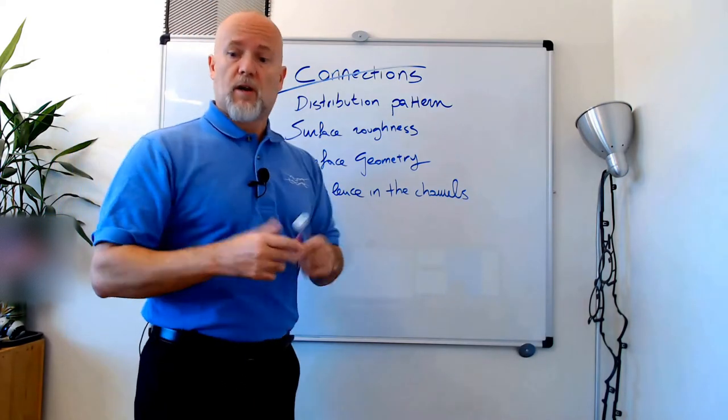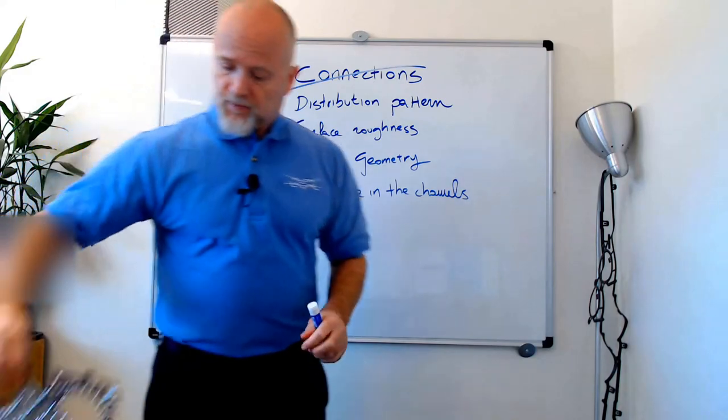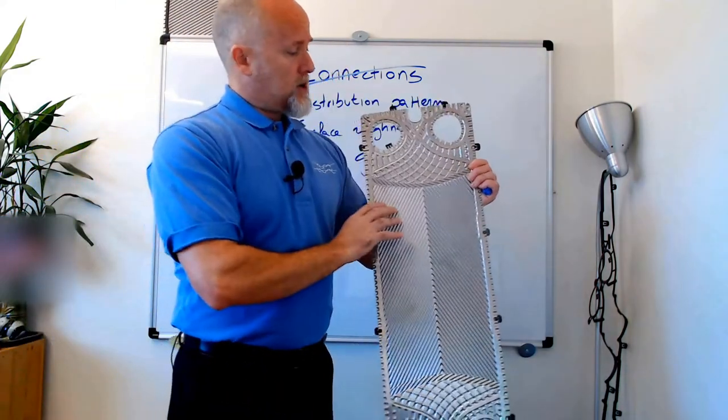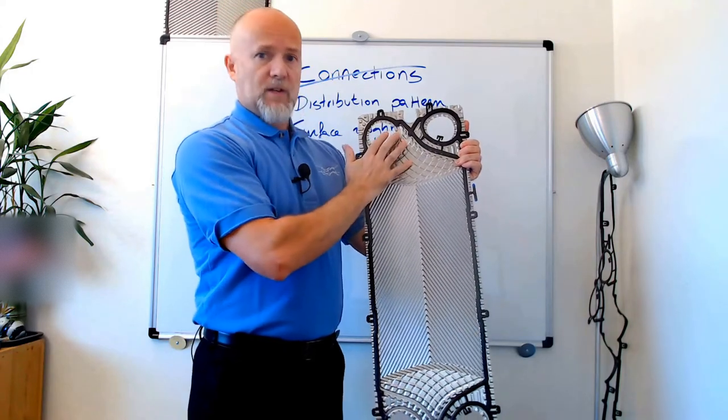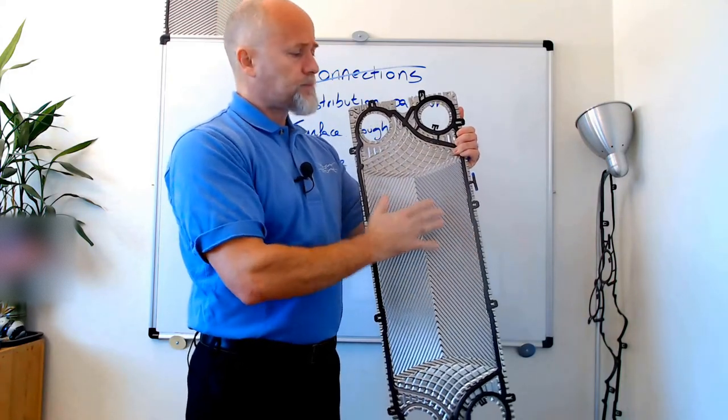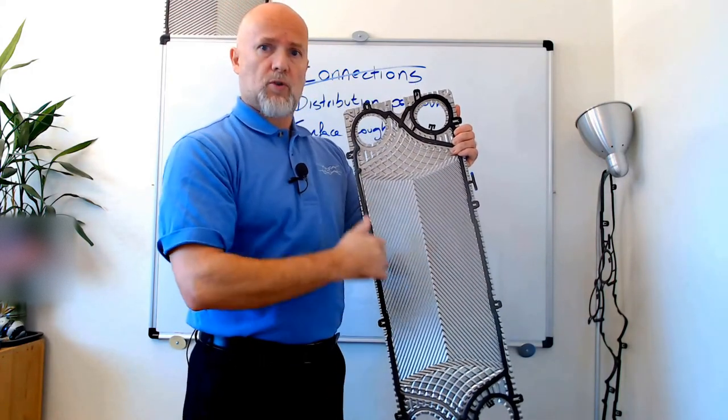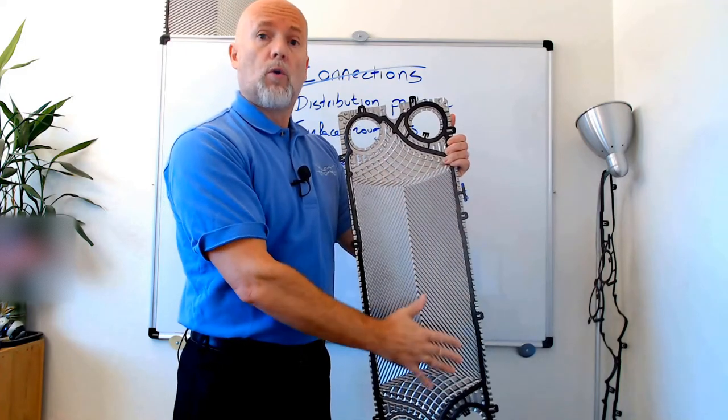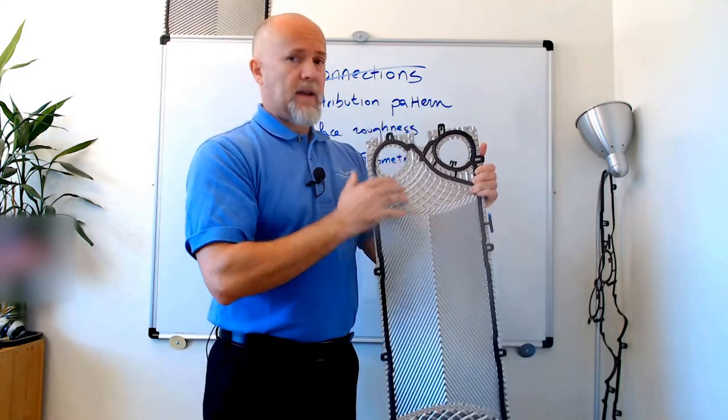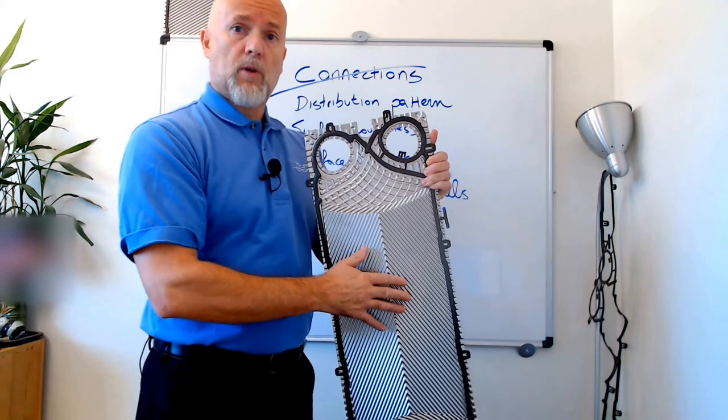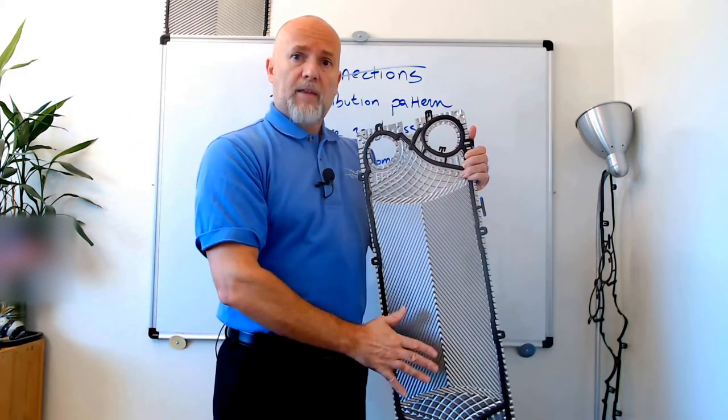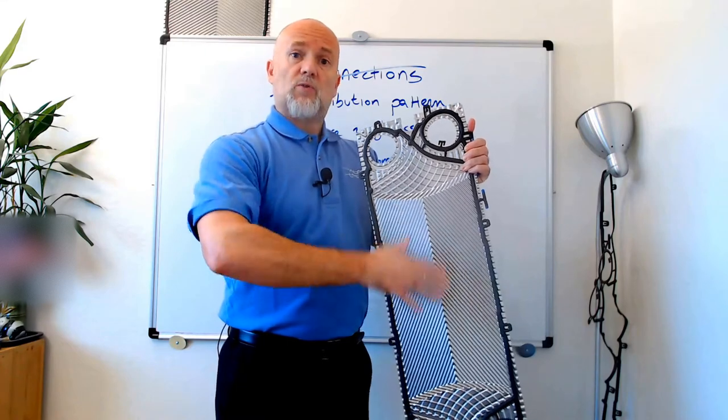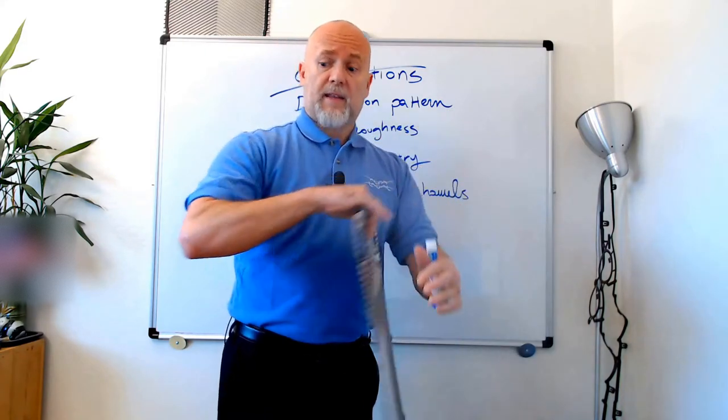You want a modern design of the plates like this one with the gaskets, which facilitates equal distribution and even distribution because you want to cover all the plate. You want a plate that is as smooth as possible so you don't have pressure drop just going through the plate, but you have pressure drop because you increase the turbulence and the shear stress.